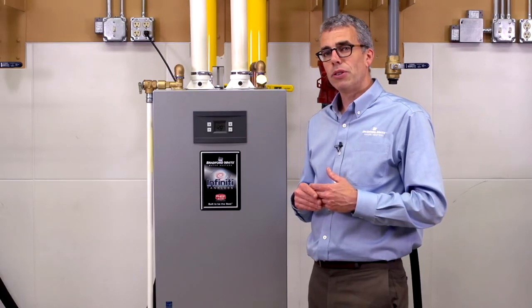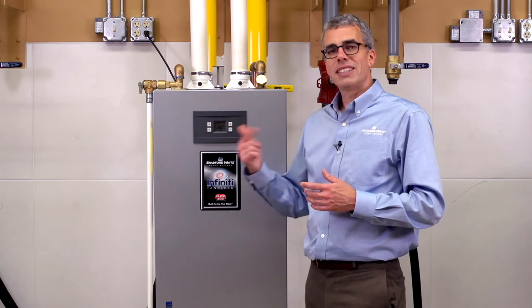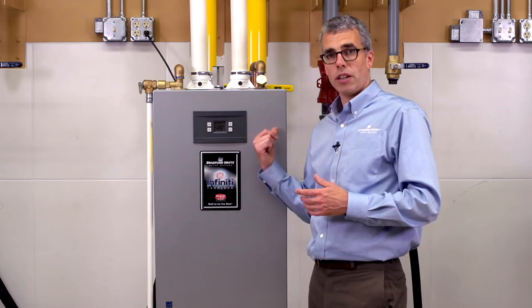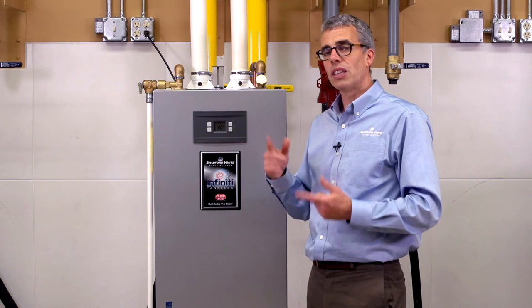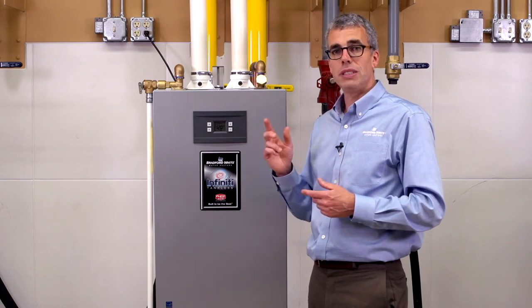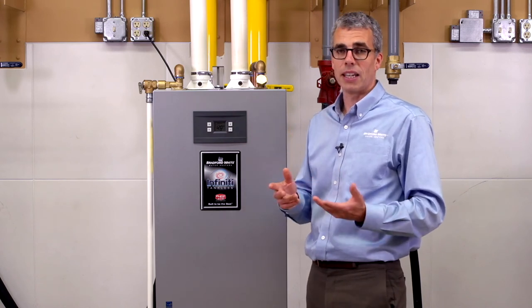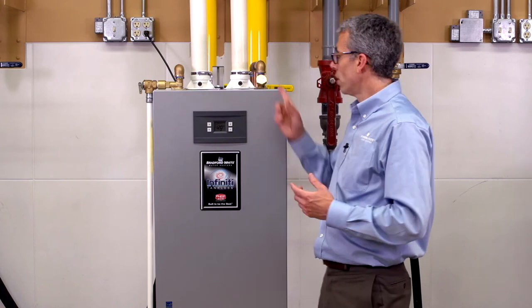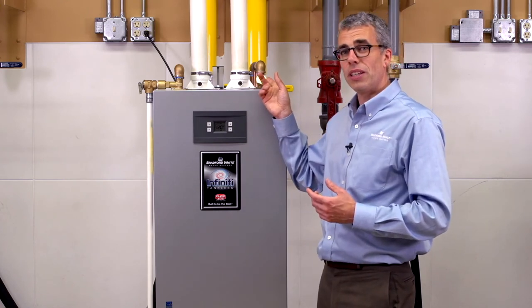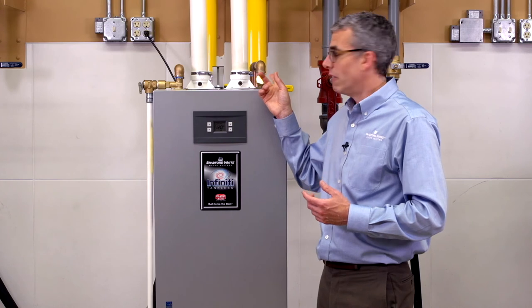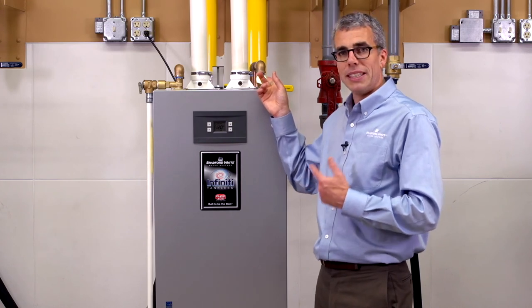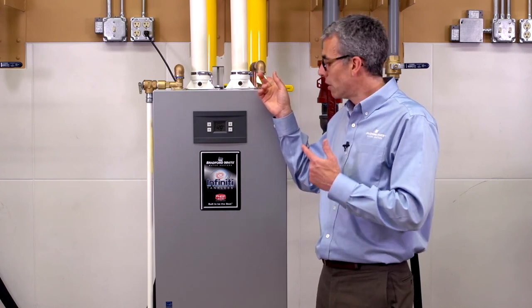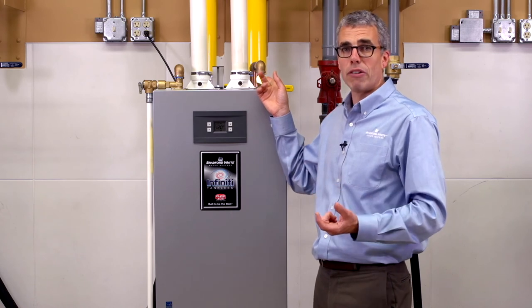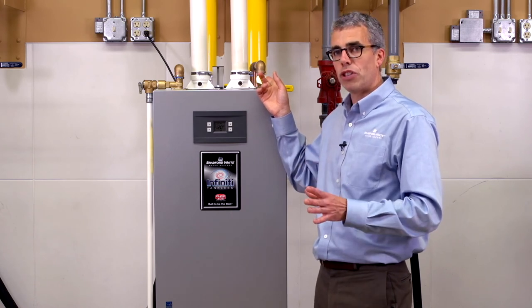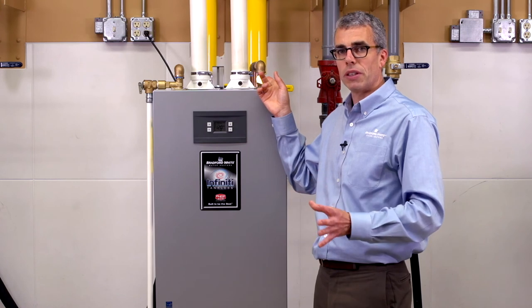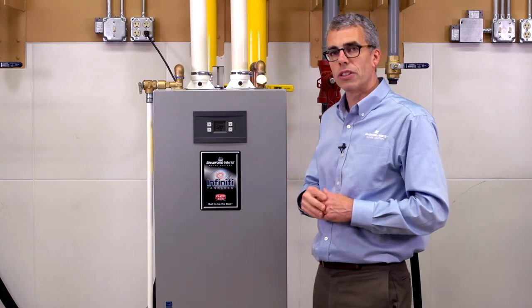So the first thing you want to do is figure out, if you turn on a second faucet, will the unit turn on? And if that's the case, then it's more than likely a flow restriction issue downstream of the water heater, let's say at a faucet aerator, or back on the inlet side of this unit at the inlet water filter. It doesn't take much to get blocked in the inlet water filter to cause an issue with a very low flow aerator in a home. So it's worthwhile checking, even if you feel like you have full flow at the fixture, double check the inlet filter always.